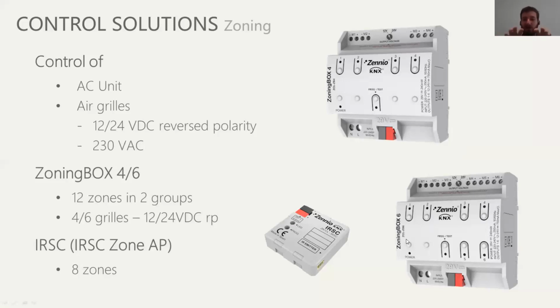So you could have 2 zoning boxes, one of them with all the logic, sending the order to all the 12 grills in the system. Now, very important with zoning box: it will send the order to the grill, and when the grill opens, it will send a response back to the zoning box. That response is really important, because that's what defines the control of the AC unit.